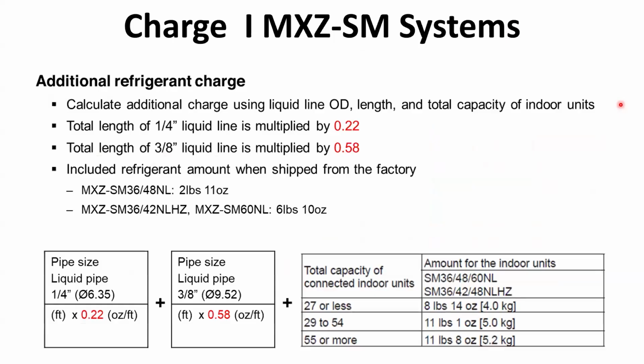So ported. And now here we're a smart multi. So again, what's changed here, it's the same, but if you look, the multipliers have changed. It used to be 0.21 on the quarter and 0.55 on the 3/8 if you're on anything but the 60. So the multipliers changed, and then what I've noticed here is the factory charge in the units now is less than it used to be.